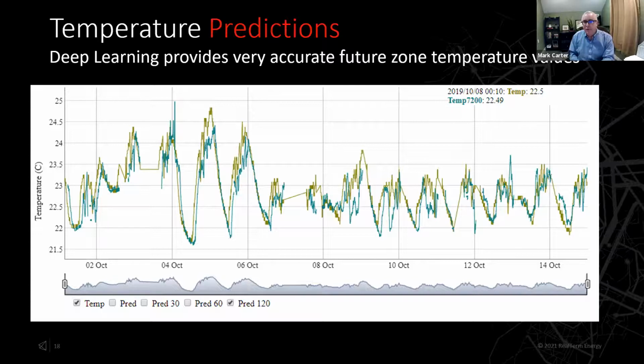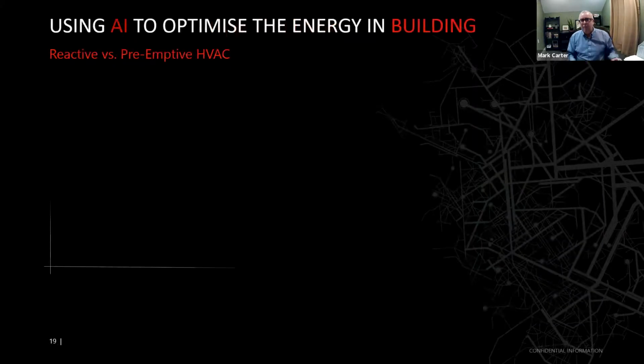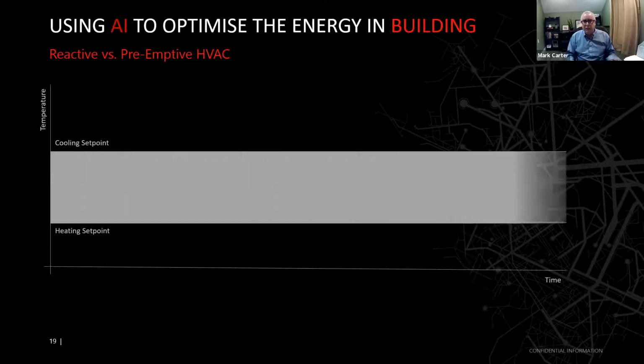So knowing what that temperature is going to be in the future, how that plays out is that in a typical HVAC system, you're going to have a cooling set point and a heating set point. So for example, if your zone temperature is set for 70 degrees Fahrenheit, your cooling set point may be 72 degrees. So if it hits 72, it's too warm. It's going to engage the HVAC equipment to actually cool the building down. And conversely, your heating set point could be 68 degrees. So if it gets too cold, it's going to engage the HVAC system to heat the building up. So that in-between zone is typically called the deadband.